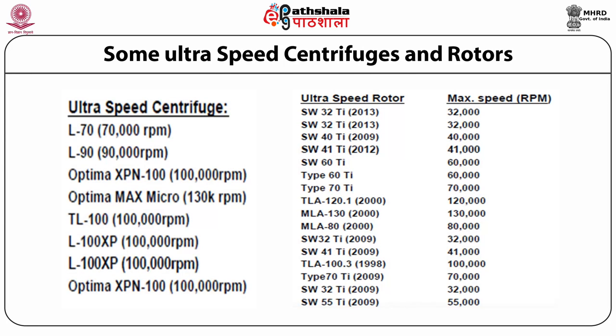Some ultra-speed centrifuge models and their speed limits: L70 model is capable of 70,000 rpm; L90 up to 90,000 rpm; Optima XPN 100 at 100,000 rpm; Optima MAX micro at 130,000 rpm; TL100 at 100,000 rpm; L100 XP at 100,000 rpm. For rotors, for example, SW32Ti was introduced in 2013 with a maximum speed of 32,000 rpm — a list of all rotors is provided with their corresponding maximum speeds.